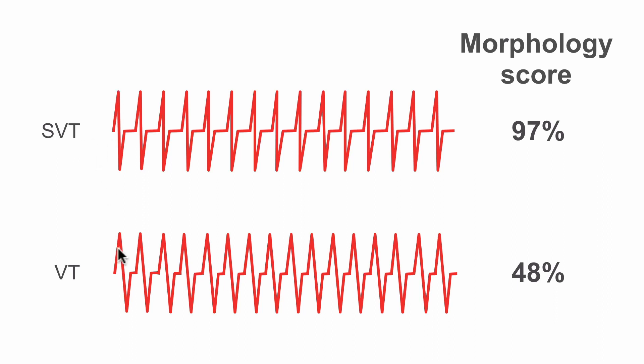If we take an SVT and a VT together in a single chamber defibrillator, we can see that actually the stability is the same, the heart rate is the same, and the onset could also be the same. They might have both started very abruptly. Now, the morphology discriminator at that point is the only discriminator available that is able to discriminate between a VT and an SVT, because it recognizes that the QRS is slightly different and actually only has a 48% match score in this example, so therapy would be delivered.